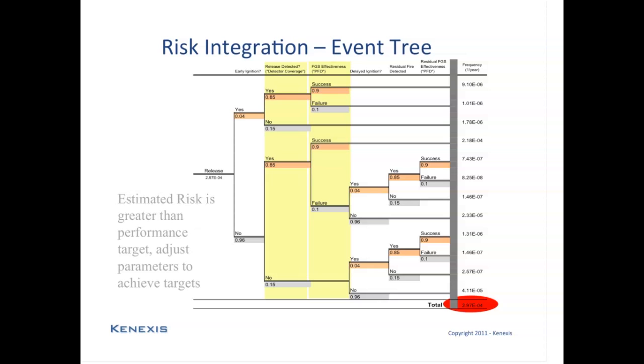And then all of the branch frequencies that result in a hazardous consequence are summed together to calculate an overall frequency. That overall frequency is then compared against the tolerable risk target. If the risk target is achieved, the design is adequate and you move to the next zone. If the tolerable risk target was not achieved, then the detector coverage and probability of failure on demand will need to be increased by manipulating the design of the fire and gas system and the number and placement of the detectors until the performance target is achieved.